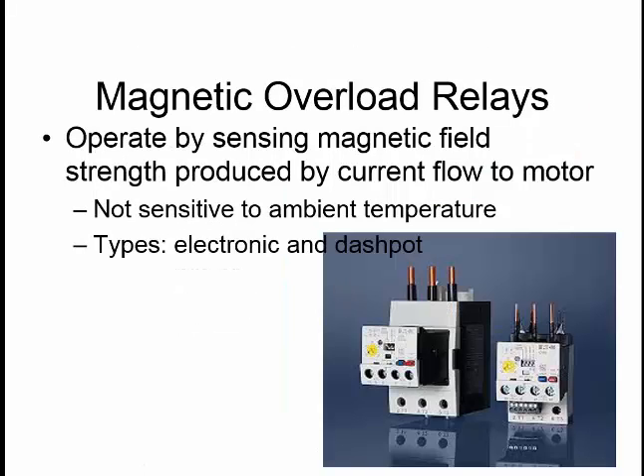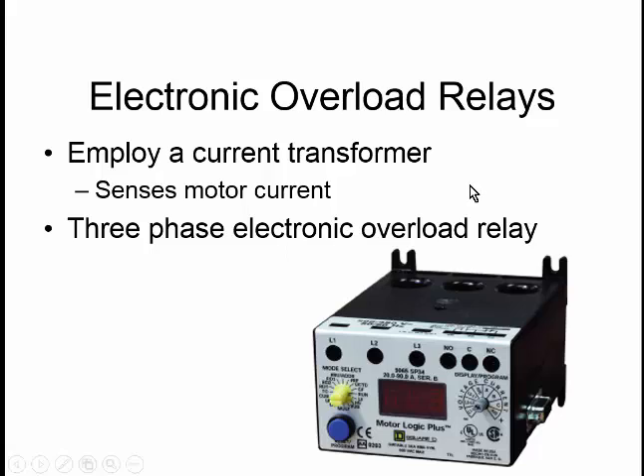Magnetic overload is controlled electronically, and instead of being heat based, it's based on the strength of the magnetic field. You can get electronic ones that are quite fancy and do a lot, but they all have the same basic principle. They sense the current, and then they trip the control circuit. Usually they do not trip the motor circuit directly, only on very small applications. That's what we saw with the manual motor starter. On very small applications, we will trip the motor directly.